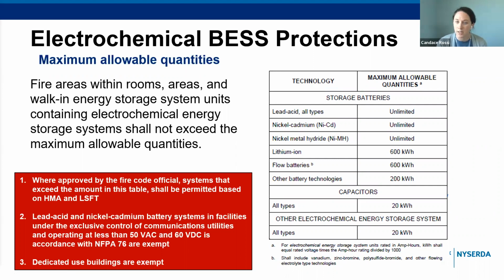There are two other exceptions. That is for lead acid or nickel batteries under the control of communication utilities and for projects that are located in dedicated use buildings. Also of note, you can see here that lithium ion systems exceeding 600 kilowatt hours will need to go through the additional testing. If you are at all familiar with NYSERDA's model battery energy storage system law, this is the reasoning for defining systems into two tiers, over and under 600 kilowatt hours. With projects over 600 kilowatt hours having many more requirements that they must meet.